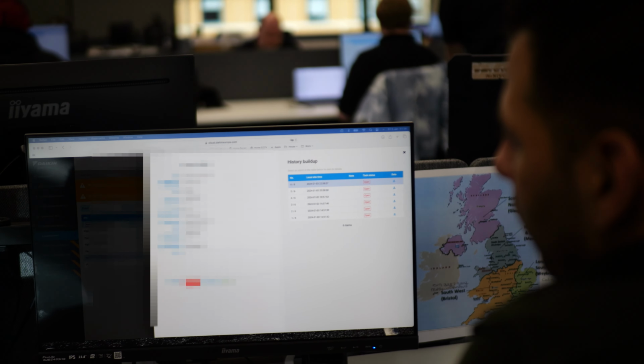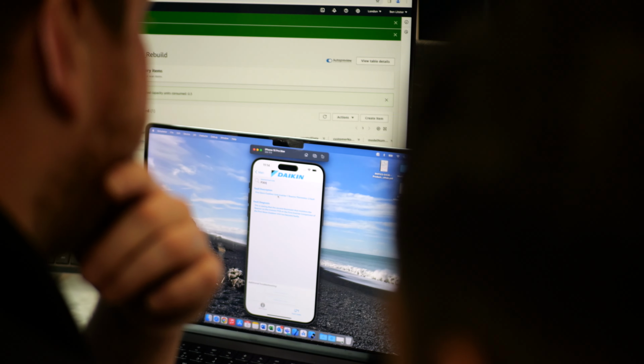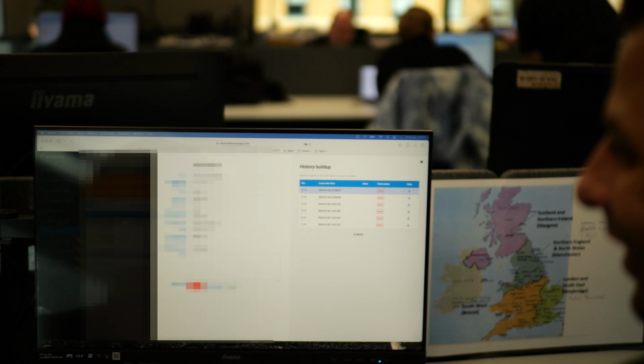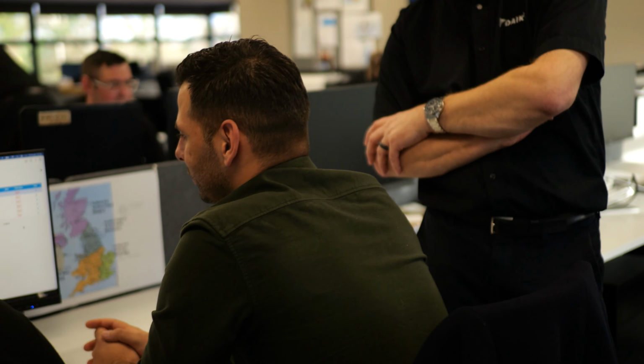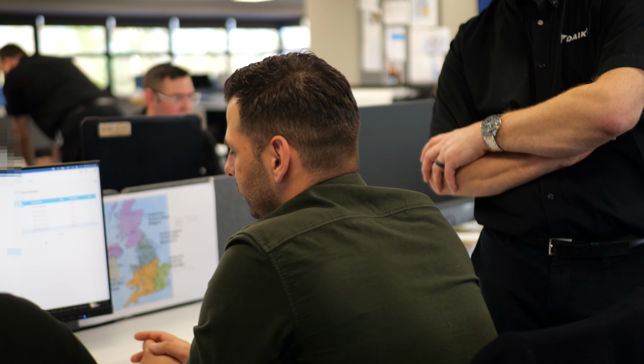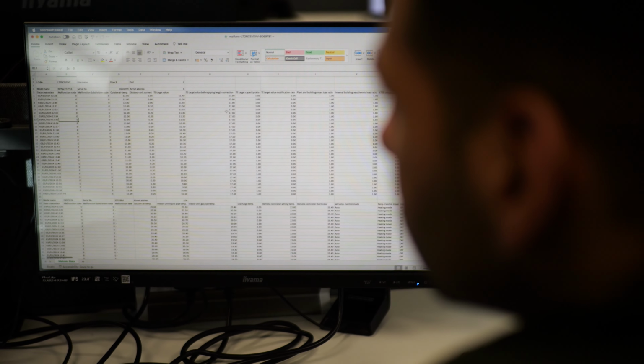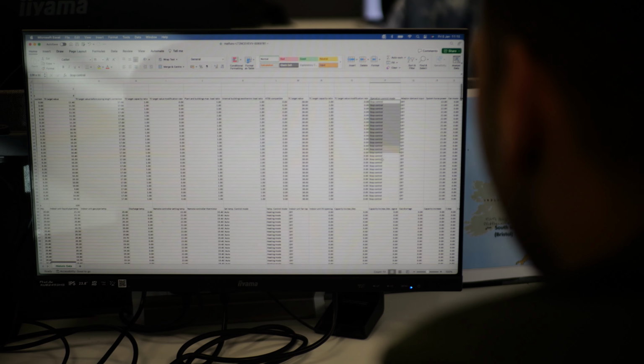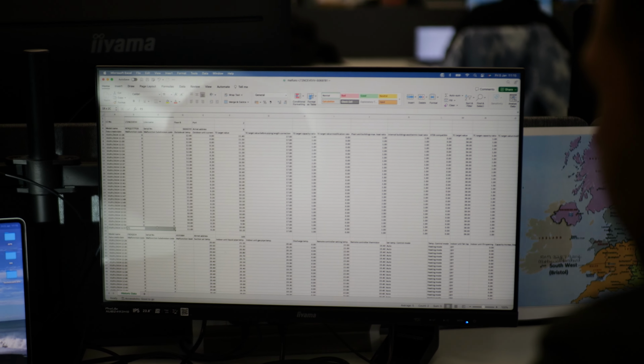Sensor error. Yeah, see, it tells you it's a P3. Wow. So that could be a sensor actually on the inverter board itself, because now they've got additional sensors. He's using his own app. So first slave outdoor unit reactor. Oh, yeah, it is. Damn. Got a thermistor issue, an inverter issue. So again, you can then look back at the original point of that. So again, that's all of our information. It wasn't actually running when it went into fault. So there is an issue with that inverter because it's flagging up a fault when it's not even on. See here, malfunction code P3 subfault 05.